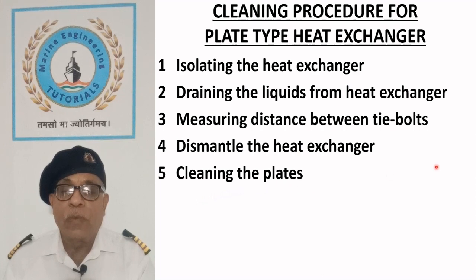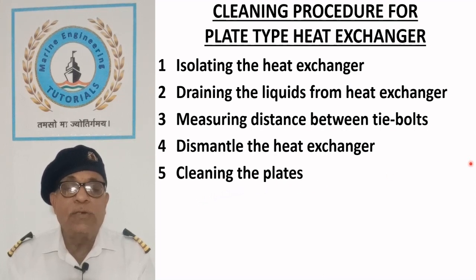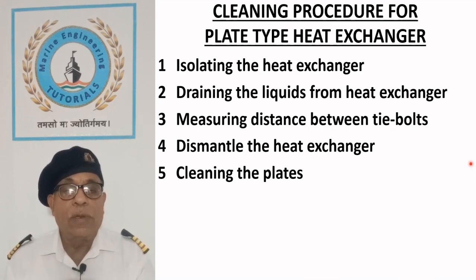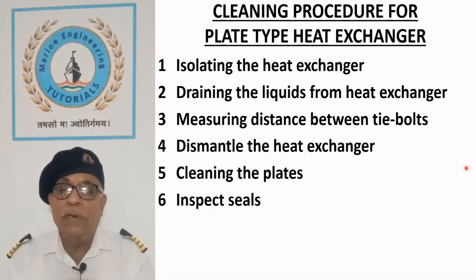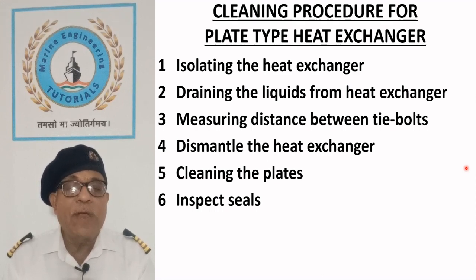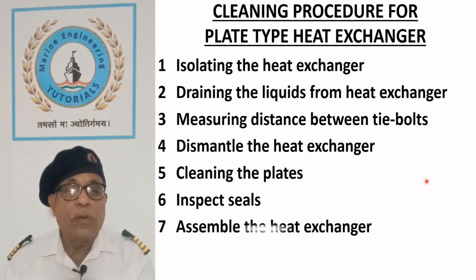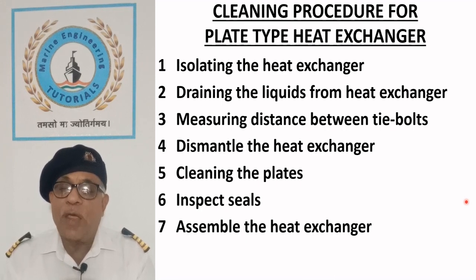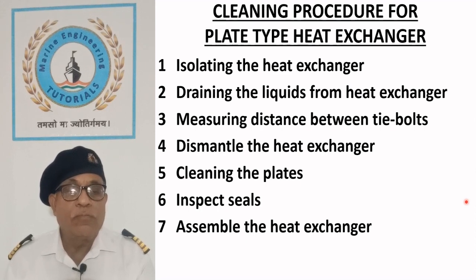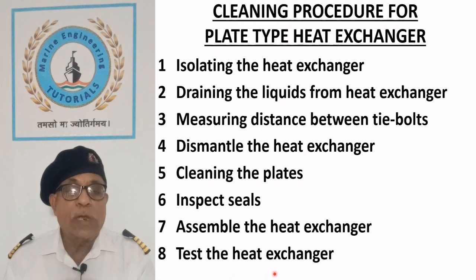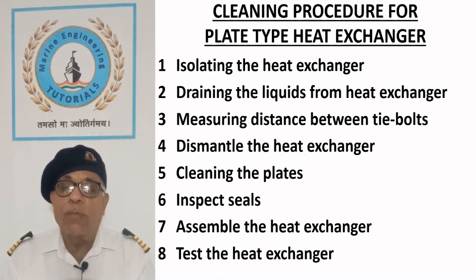Cleaning the plates. Clean the plates on both sides by soft brush and water. Inspect seals. Pay special attention to the seals and look for any damage. Assemble the heat exchanger. Assemble the heat exchanger by tensioning the tie bolts to the original measurement. Test the heat exchanger. Close the drains for both liquids and start their flow one by one while purging the air. If no leakage is observed, the heat exchanger is ready for use.